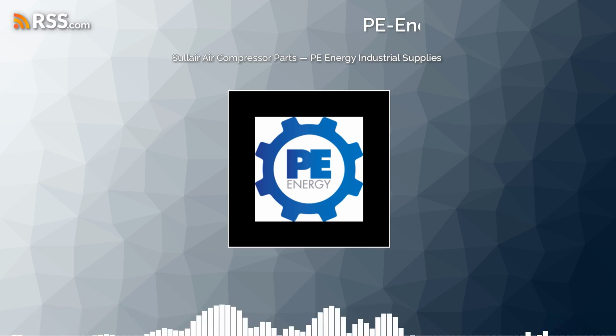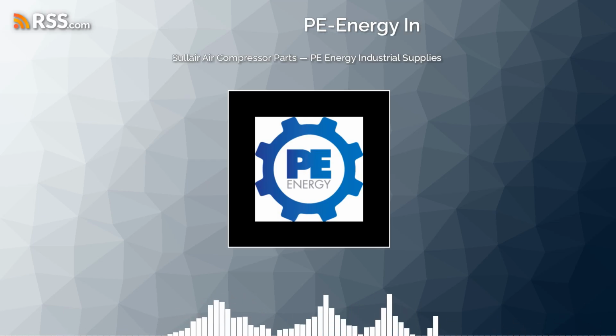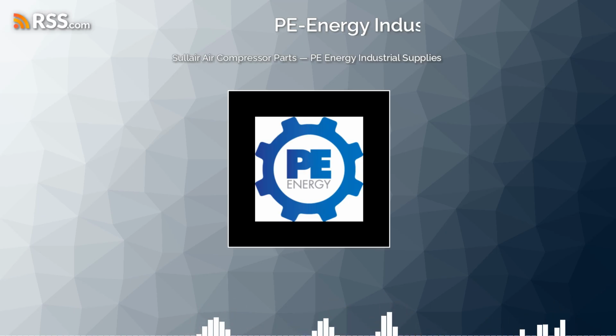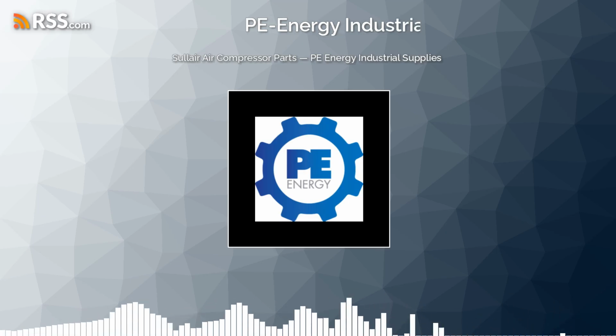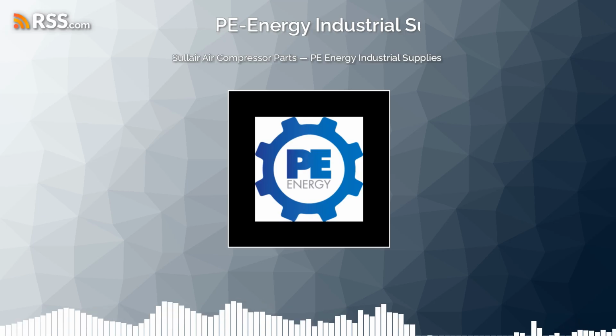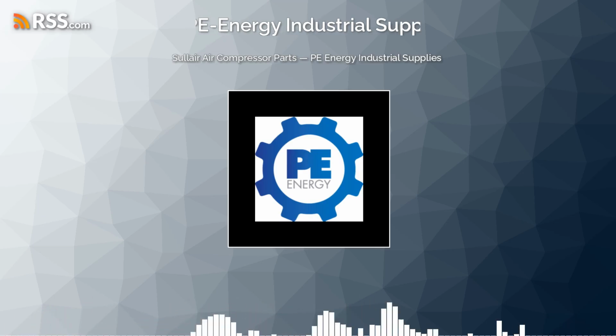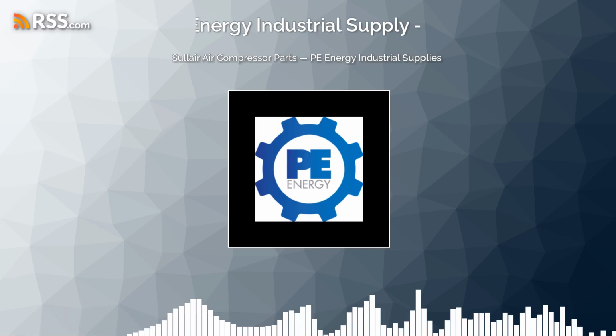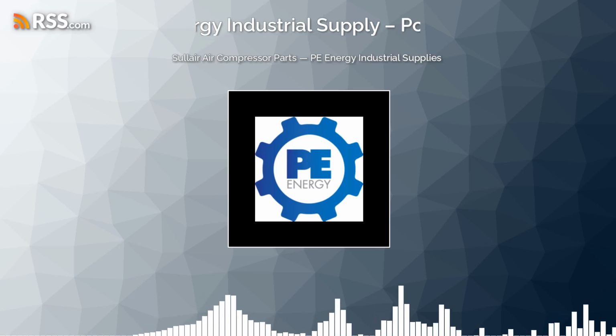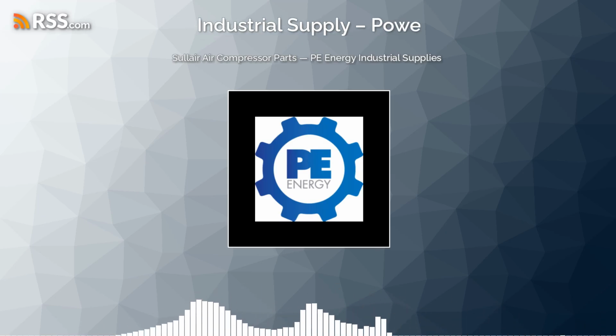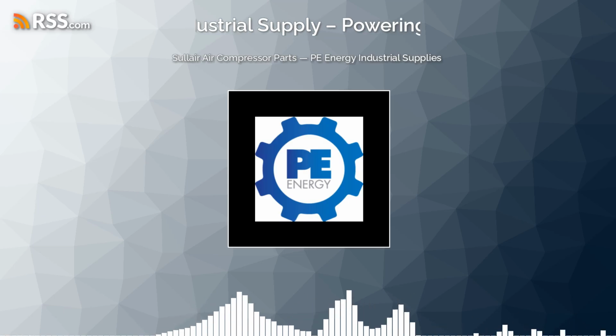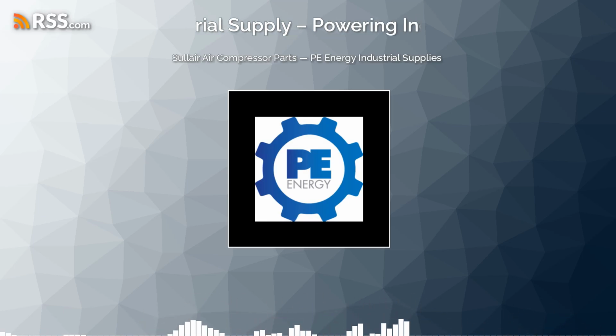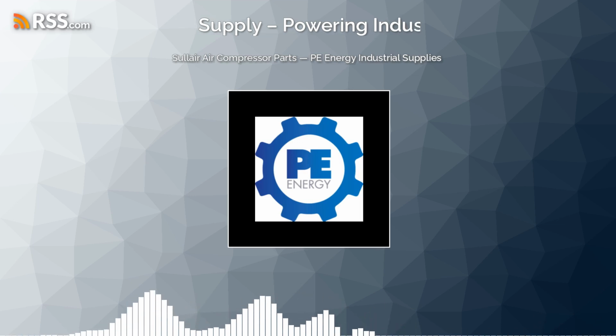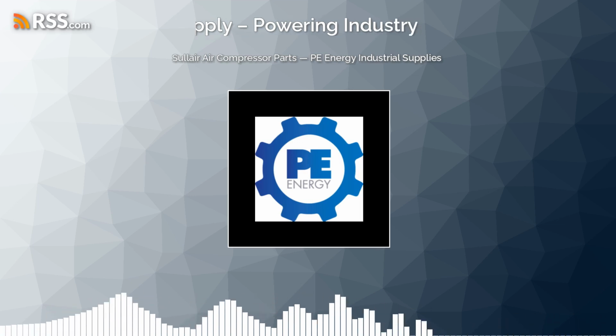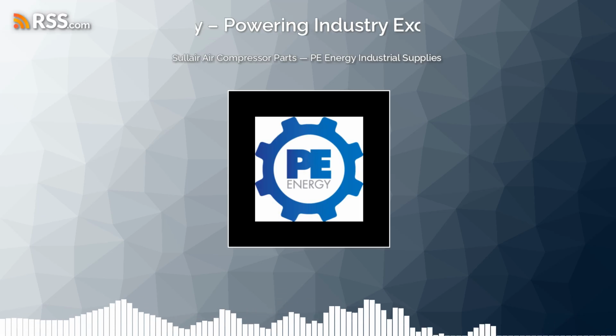It really is. The borosilicate matrix intentionally creates fluid dynamic chaos. It forces these ultrafine vapor-like aerosols to collide and combine, until they form a liquid droplet large enough and heavy enough that the moving air can no longer carry it. Right. And at that exact moment, gravity takes over. The heavy, newly formed droplets of oil and water physically slide down the outside of the stainless steel element and drip into the bottom of the housing. Okay, so you've effectively engineered a way to turn a high-speed, invisible mist into a manageable physical puddle of liquid.